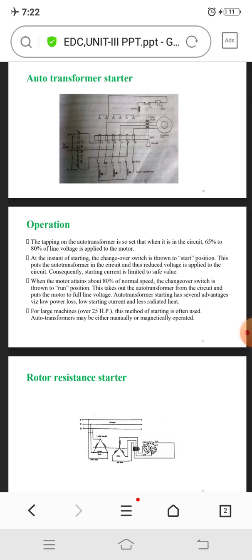At the instant of starting, the changeover switch is thrown to start position. This puts the auto transformer in the circuit and reduced voltage is applied to the motor. Consequently, starting current is limited to a safe value. When the motor attains about 80% of normal speed, the changeover switch is thrown to run position. This takes the transformer out of the circuit and puts the motor on full line voltage.